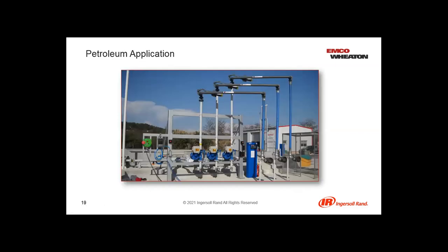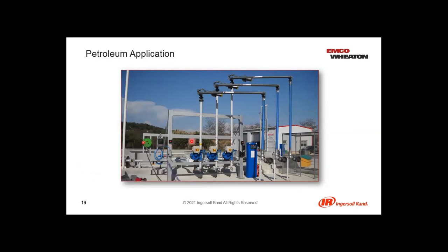The most common bottom loading arm is the one used for loading white products. It could be like on the picture with hoses, with API Covington coupler, GO452 or the new GO453. And so we can see that it's really simple. We have the metering system, a grounding device, monitor control for the probe, the overfill device. And we have only three loading arms, one for gasoline, one for gas oil, and one for fuel oil.